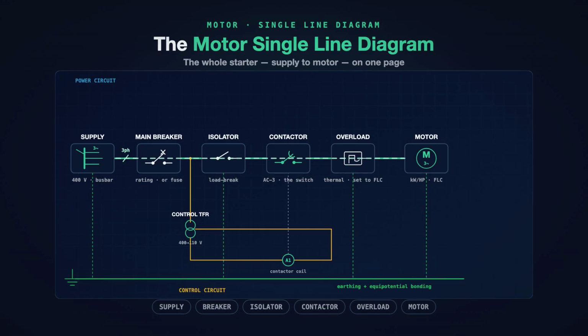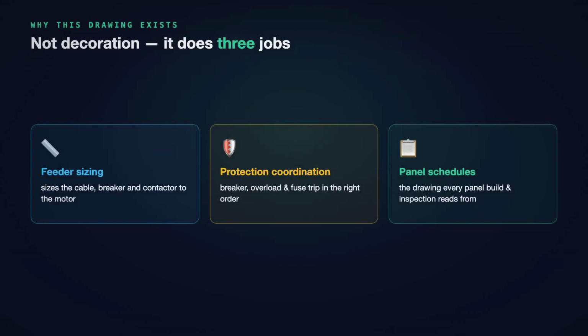So let us rewind it and build this motor single-line diagram up block by block: supply, breaker, isolator, contactor, overload, motor, so that by the end you can read one at a glance and draw your own. First, why this drawing exists at all. You may have seen a generic single-line diagram before. One line standing in for all three phases of a system. This is that same idea, aimed at one job, a single motor feeder and its starter.